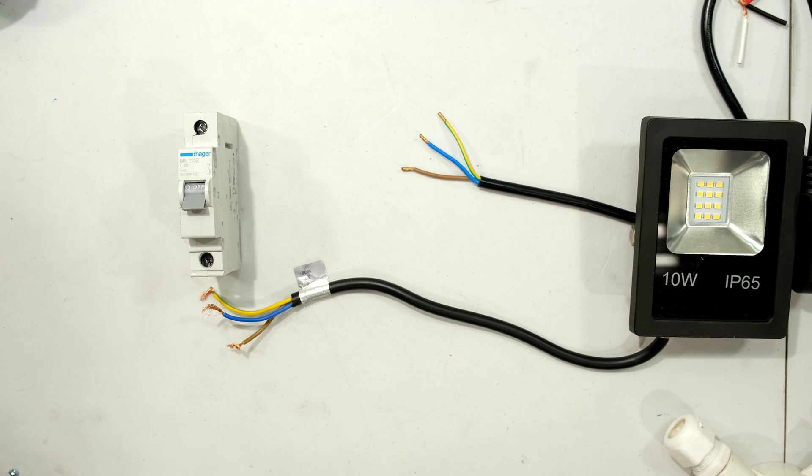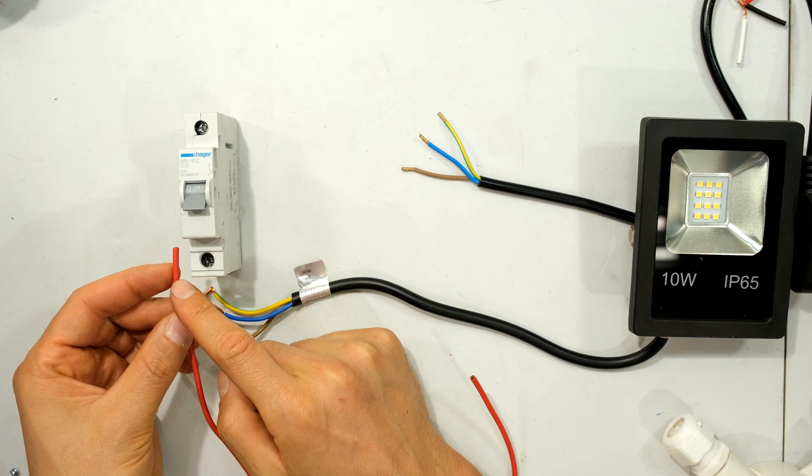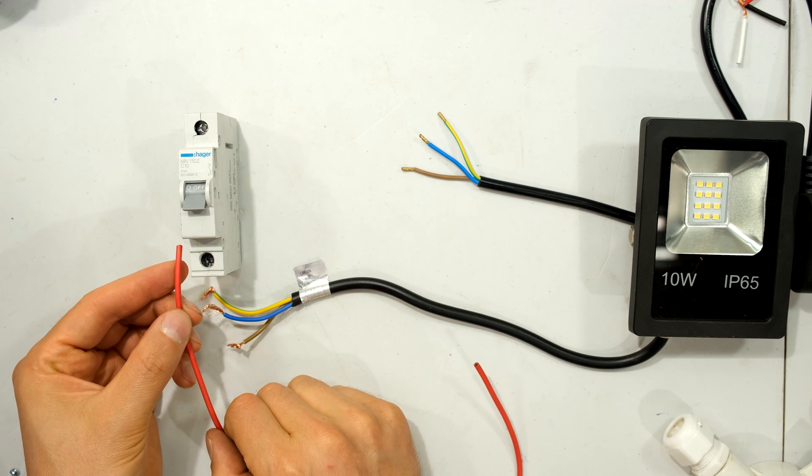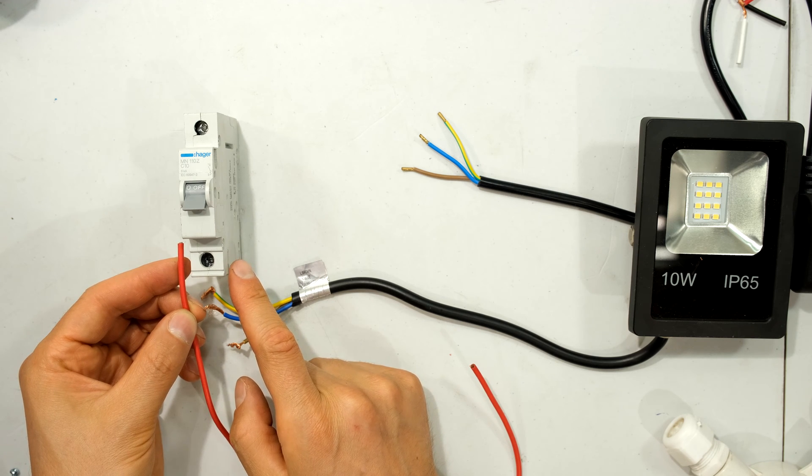Now the wire size is very important. For example, this is a 1.5mm wire and this is a 10A circuit breaker. This wire is sufficient for this breaker running at 220 or 230 volts.